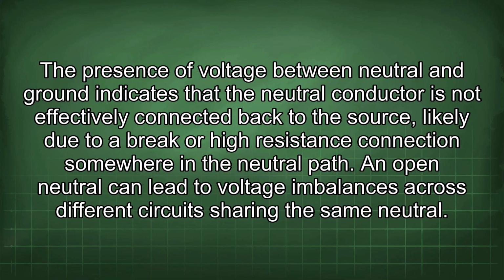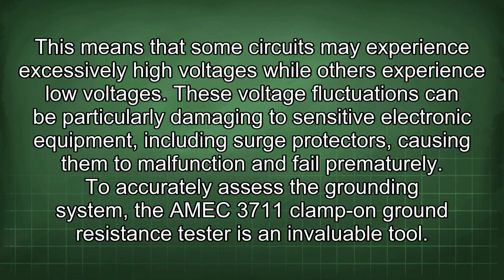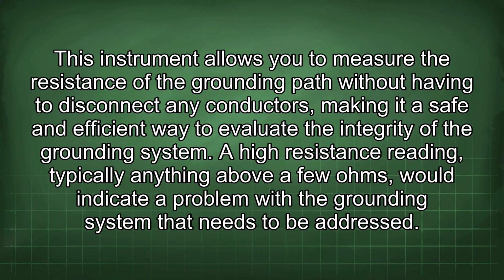An open neutral can lead to voltage imbalances across different circuits sharing the same neutral. This means that some circuits may experience excessively high voltages while others experience low voltages. These voltage fluctuations can be particularly damaging to sensitive electronic equipment, including surge protectors, causing them to malfunction and fail prematurely. To accurately assess the grounding system, the AMEC 3711 clamp on ground resistance tester is an invaluable tool. This instrument allows you to measure the resistance of the grounding path without having to disconnect any conductors, making it a safe and efficient way to evaluate the integrity of the grounding system.